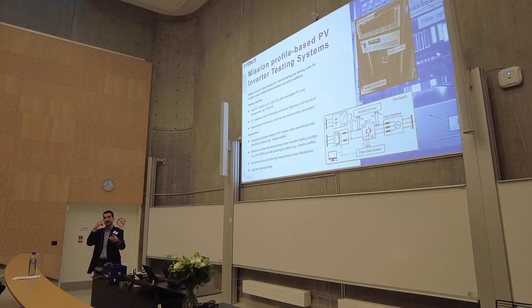Another example is related to testing for motor drives. The concept is the same: we simulate all the rest, the rotating machine. We have a more powerful inverter simulating the load, the torque, the speed, and what happens on the mechanical side, with a grid simulator on the other side, and the inverter tested in between. We can subject it to a customized mission profile and monitor semiconductor temperature.